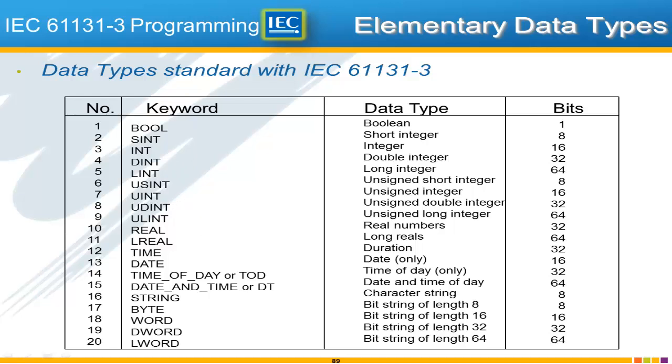And within IEC 61131, you'll hear the term strict data typing or strong data typing. And what this generally means is that any changes of data type will be shown in the code. You will not have in IEC 61131 automatic assumption of any conversion of data types.